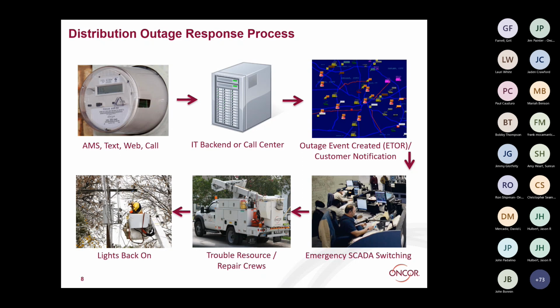One clarification: the system protection is meant to clear a fault. In the case of a tree hitting a line, there's protective equipment upstream, not necessarily where the tree hit the line, that's going to detect a hard fault and open, and that de-energizes the line. That system protection is what clears the immediate danger of having the line energized.